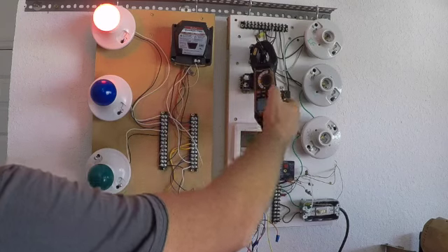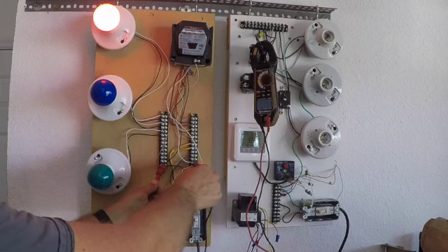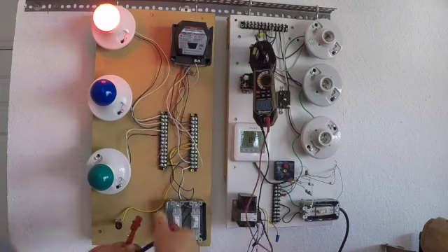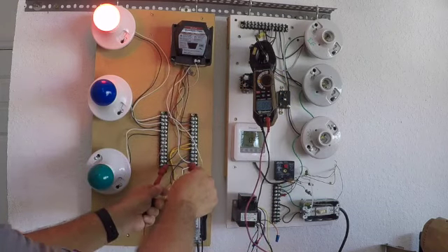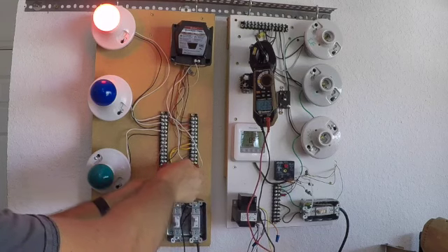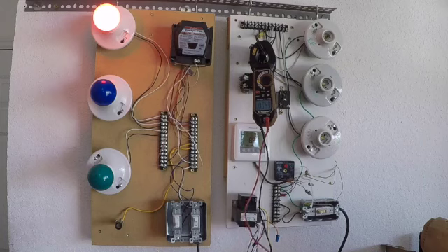Let me turn a light on here. So my incoming voltage, between line and neutral, measures out to 123.9. Now, we know that our voltage is classified as 120, 240, 480, but the power company does have a leeway of plus or minus 10 volts, actually it's 10%. So we can have 123.9 on a residential circuit very, very easily.